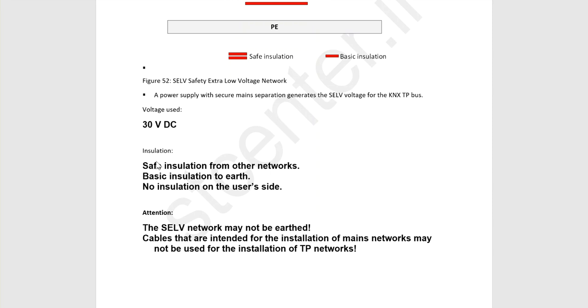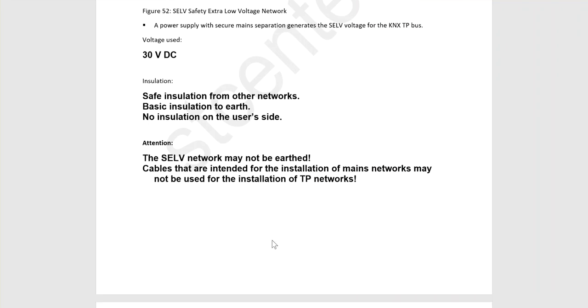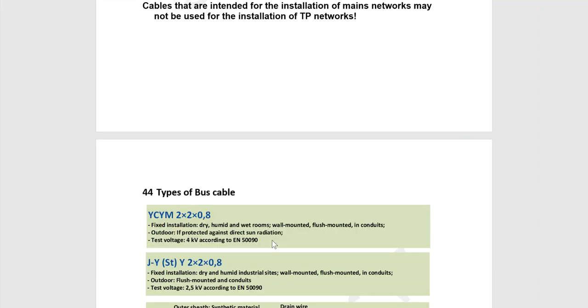So how about the insulation? The book also said there is a basic insulation to the earth, as I said. There is a safe insulation or double insulation to other networks, like 230 volts or other networks, and no insulation to the user side. The SELV network may not be earthed. So in KNX we do not earth the KNX cable. I mean, the KNX cable most of the time has a shield. We do not connect the shield to the earth. Cables that are intended for the installation of the mains network may not be used for the installation of a TP network. The special thing in KNX is that we should only use the KNX cable for the connection.